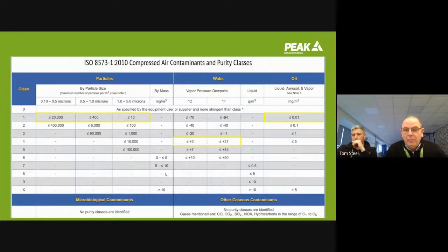The next one is vapor. Now, we normally use a refrigerated dryer. A refrigerated drying system will give you approximately 3 degrees C dew point, and that's exactly what we want. And then the other one, we look at liquid aerosol or vapor oil. To get these high volumes of air, the compressor will generally be an oil-filled screw compressor. So we have to make sure that oil vapor is removed from the system before it gets to the O2 generator.